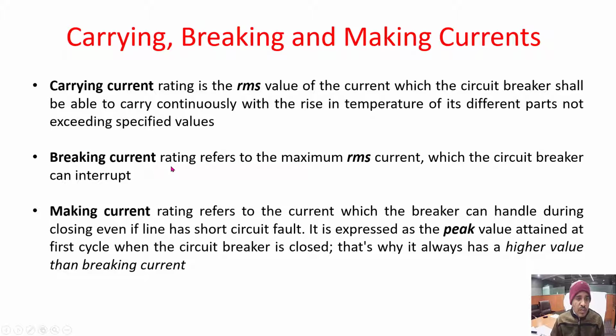Then the breaking current rating refers to the maximum RMS current which the circuit breaker can interrupt. That means, when the circuit breaker has to interrupt the circuit, what is the maximum RMS current that it can interrupt without any problem.